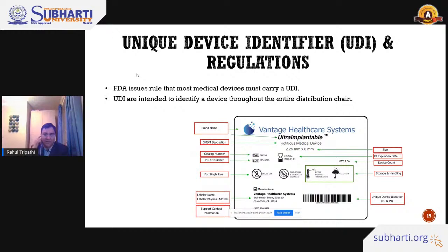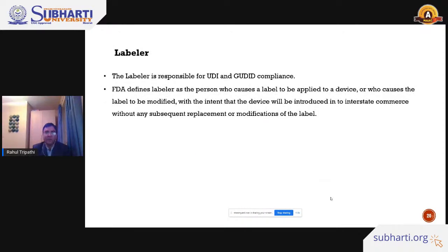I'm giving an example here of the UDI. You can see there's a barcode at the bottom of this picture, which is the UDI number, basically a UDI barcode. The UDI is the combination of the DI and PI. I will explain what the DI and PI are in the next slide. So this is one example of the UDI. You can scan this barcode and easily identify all the information related to this medical device. Some medical device manufacturers put more information around the label, but UDI is compulsory and mandatory from the FDA.